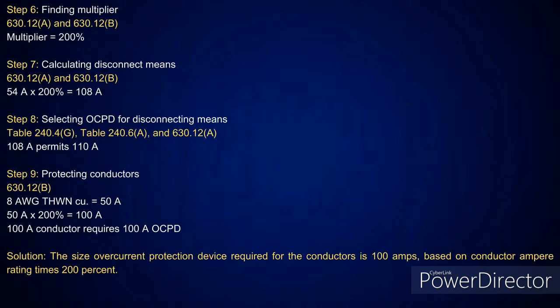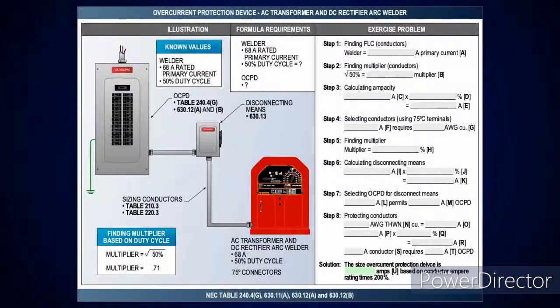So I cross-check myself, and I could have just dropped down because I did go at the 200%, but I just went up to 110 amps to sort of show you. A lot of people will say, I'm going to go up to 110, but really, would I be able to go down to 100 amps, like it's saying not to exceed it? Well, sure, because I just put 50 amps on at 200%, which gave me 100 amps. Right. So that is a good way of learning here. And you're learning the proper procedures to do these calculations.